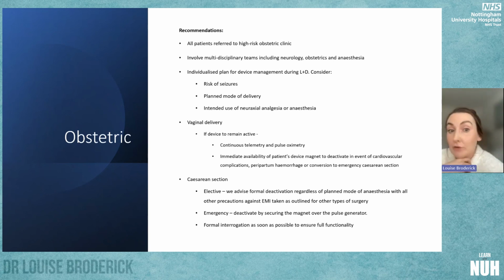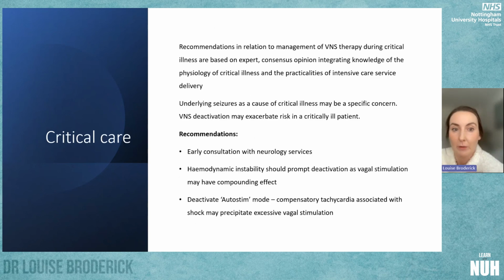For vaginal delivery, if the device is to remain active, we recommend that continuous telemetry is used to monitor maternal heart rate and have immediately available the patient's device magnet to rapidly deactivate the device if necessary. We advise for elective cesarean section to deactivate the device, and in an emergency, you can use the patient's own magnet to deactivate the device. Of course, it should be formally interrogated. With respect to critical care, very briefly, it is slightly complicated in that these patients may be presenting with seizures as the underlying cause of critical illness, but equally if a patient is hemodynamically unstable, there is a risk that vagal stimulation could compound this effect.